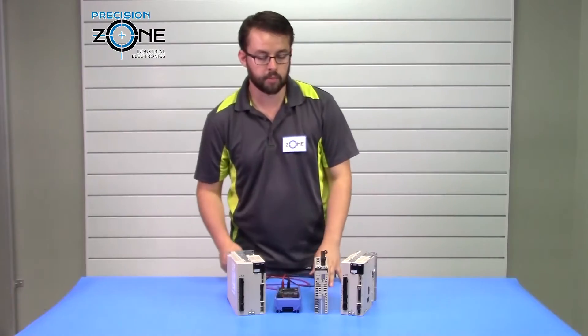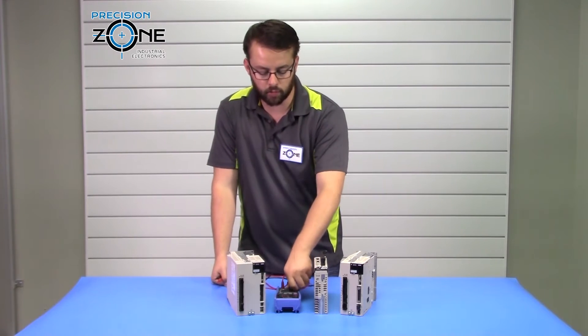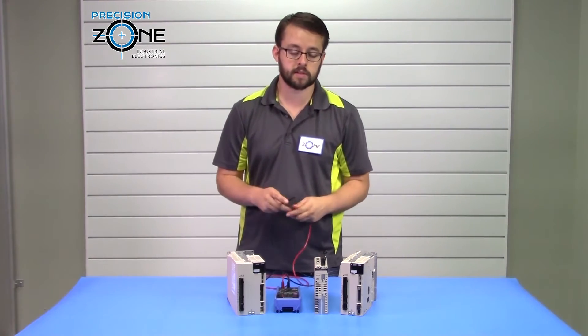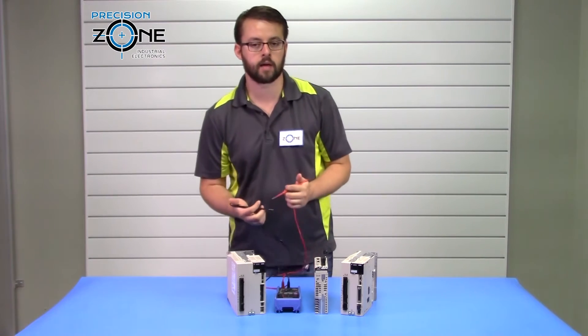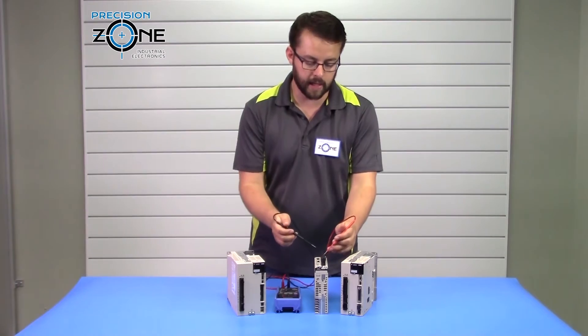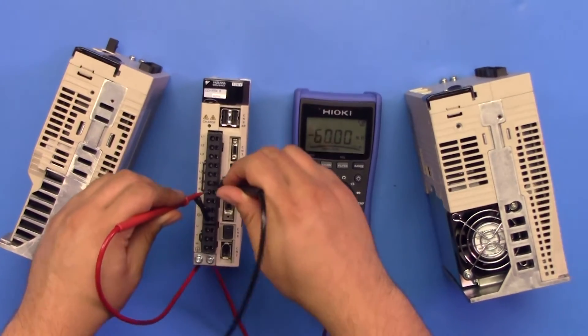So that verifies that your inputs have not blown up or have been shorted. Then you're going to want to switch your digital multimeter to the resistance check function, and you're going to want to check the resistance of your regen resistor to verify that it has not been burned out.